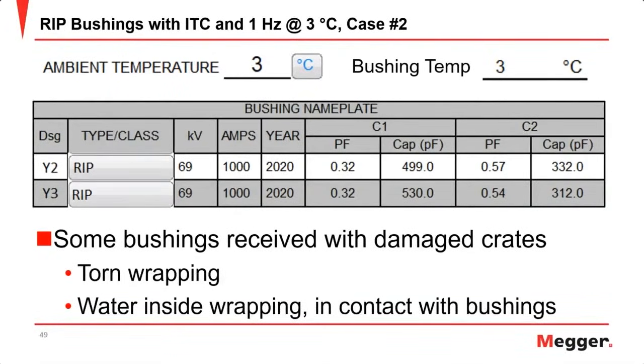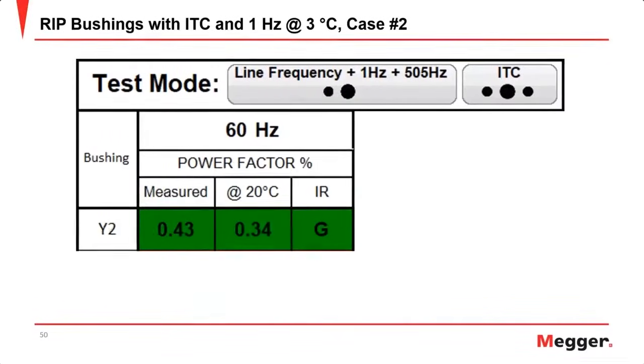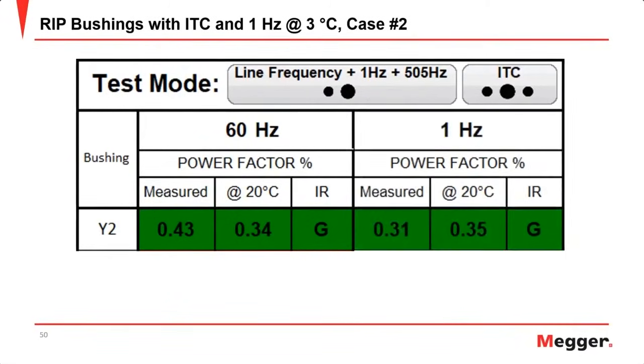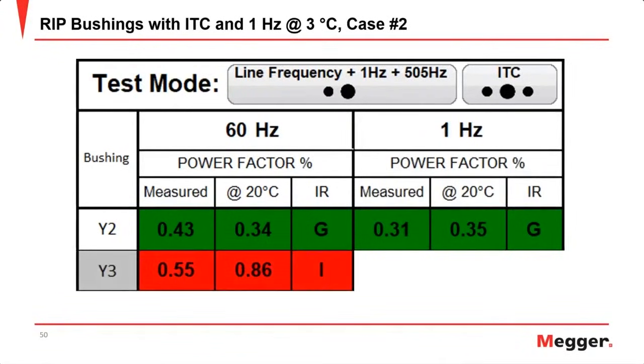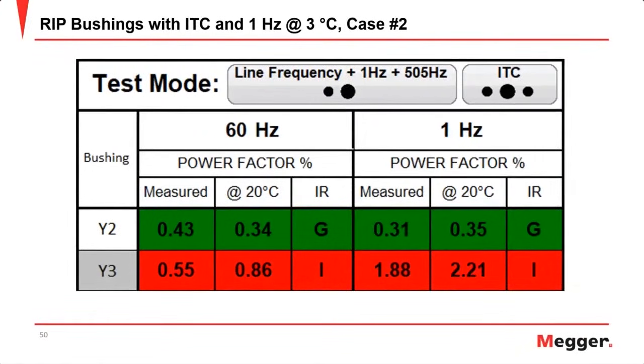And what they found for 2 particular bushings that we're focusing on out of the 9 that they tested is that they had 1 bushing that measured good at 60 Hertz, and it also measured good at 1 Hertz. And then another bushing that measured high at 60 Hertz, and then also measured high at 1 Hertz. So again, using this 1 Hertz in 2 different ways to confirm good 60 Hertz power factor measurements and to confirm bad 60 Hertz power factor measurements.